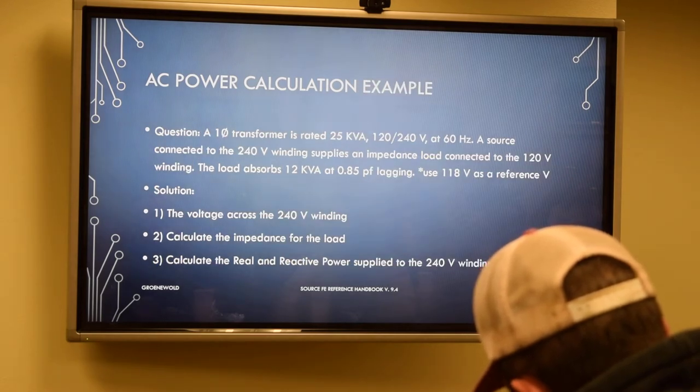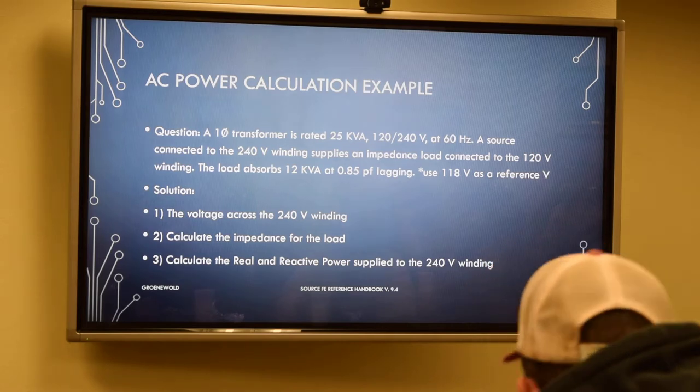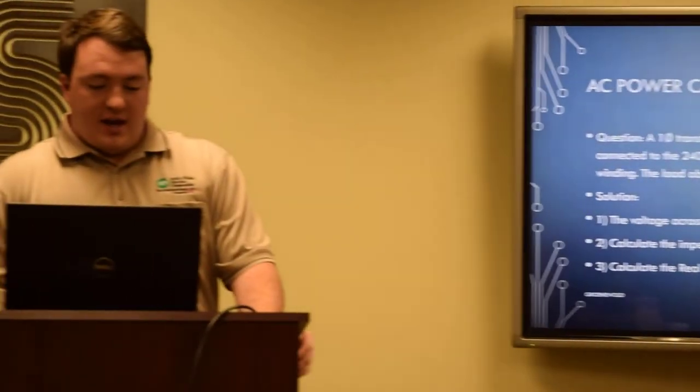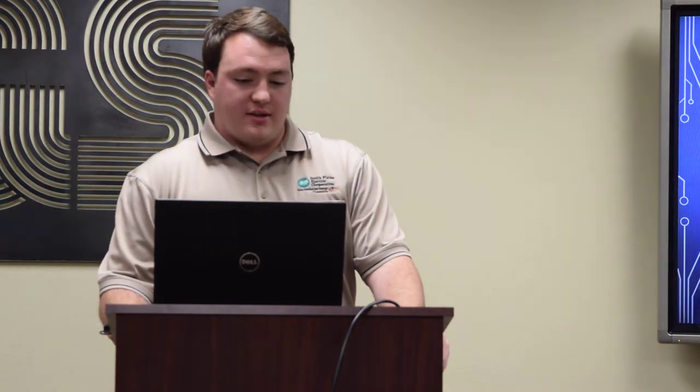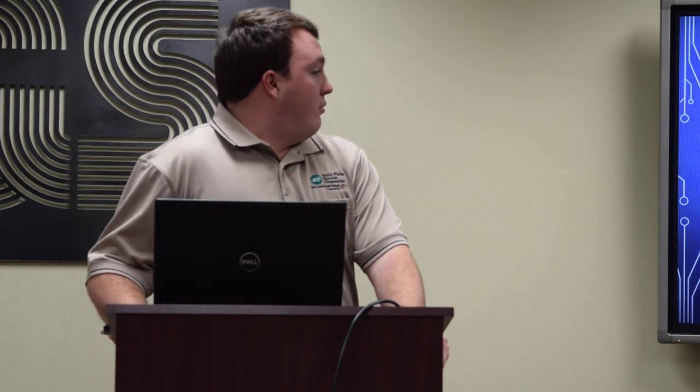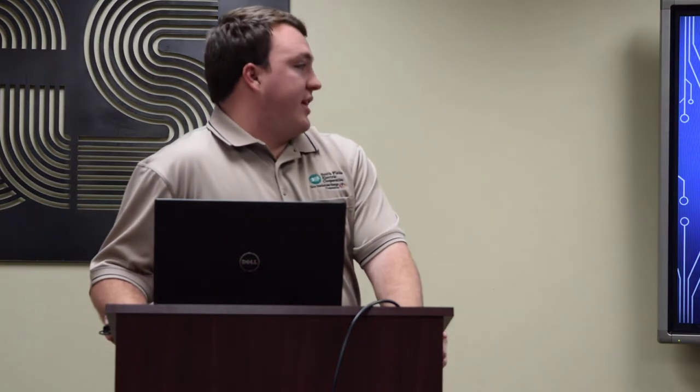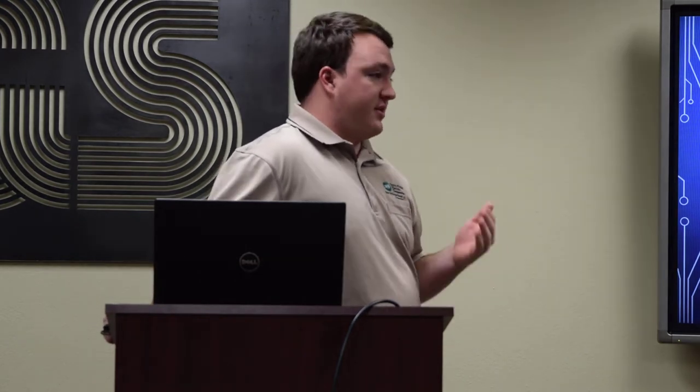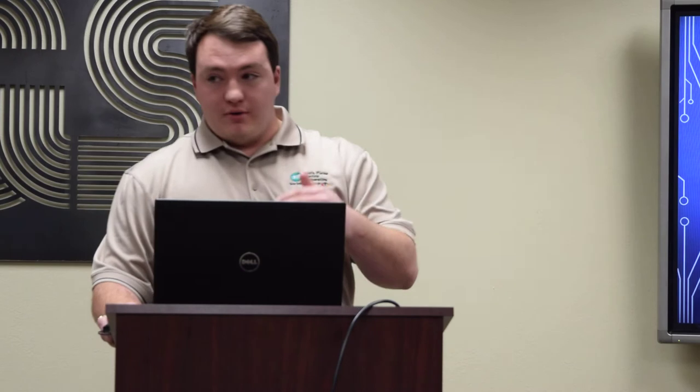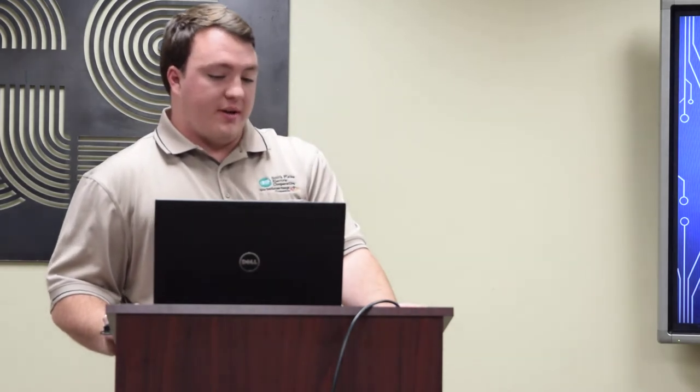So here's an example. A single phase transformer rated at 25 kVA, with a 120/240 volt at your normal frequency. A source is connected to the 240 volt winding, which supplies an impedance load connected to the 120 volt winding. The load will absorb 12 kVA at 0.85 power factor lagging. We're going to use 118 volt as a reference voltage. Because any time you go out there and measure it, it's not always 120, it's close. I'm going to walk you through how we would calculate the voltage across the 240 volt winding, the impedance for the load, and then the real and reactive power that is supplied.